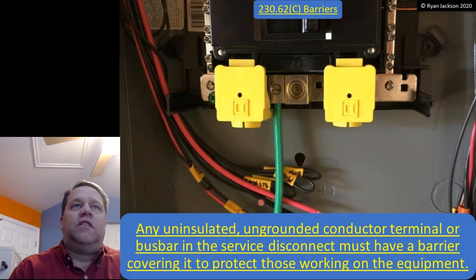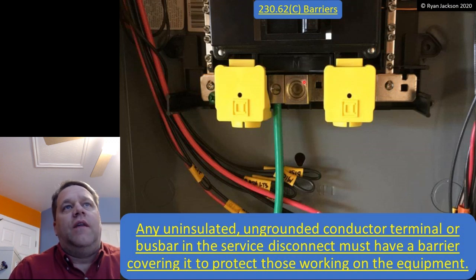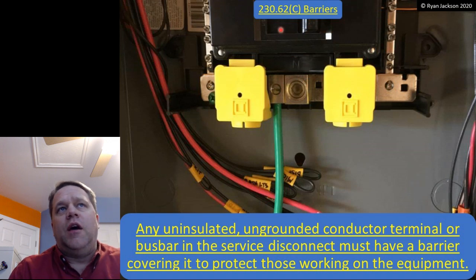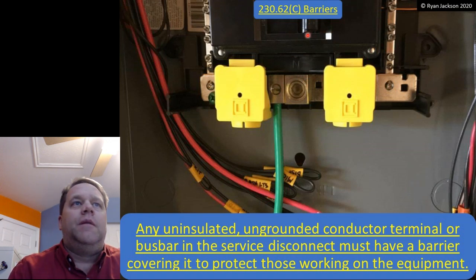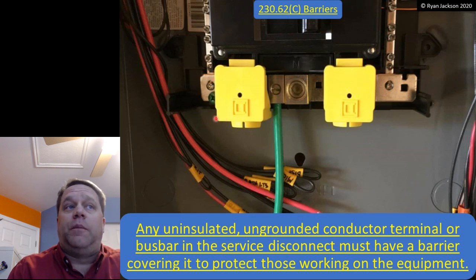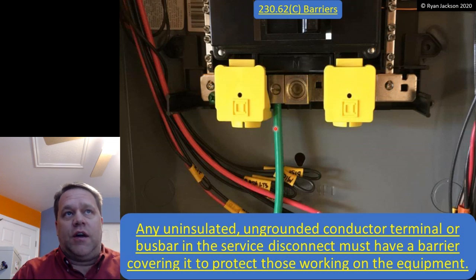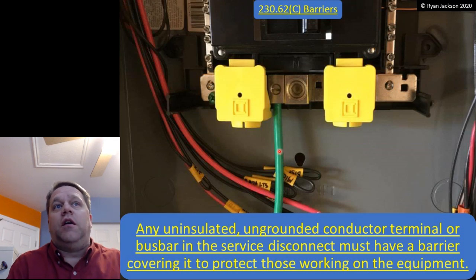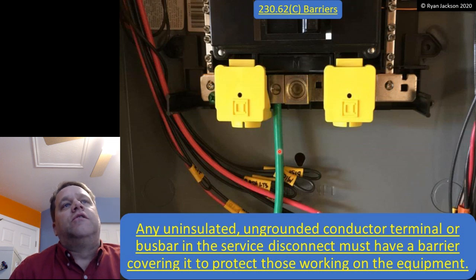Okay, this is my service disconnect. It's important that we understand that. So right there is how I shut off my service. That's my 200 amp breaker or whatever it might be. You can see back here, we've got the green screw, the main bonding jumper, which is only at the service disconnect. We've got a grounding electrode conductor, which, generally speaking, is only at the service disconnect. So these are my terminals for the service conductors.